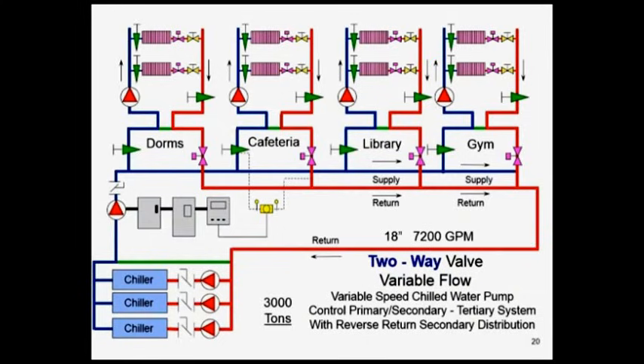The point is the total flow through the distribution is going to be 7,200 GPM. Yet you go to that dorm, you got to set it up for 2,400 GPM. You got to set up the cafeteria for 24. So you best know what you're doing here. Your total flow to distribution is only going to be 7,200, but you got to be able to give each building 2,400. And that's what I mean by having a simple system sketch and understanding the intent of the engineer, understanding what you're trying to do.